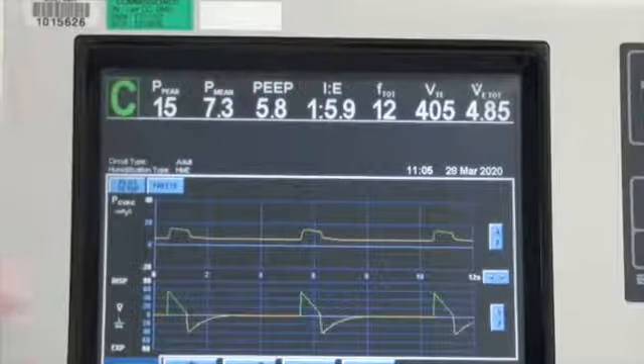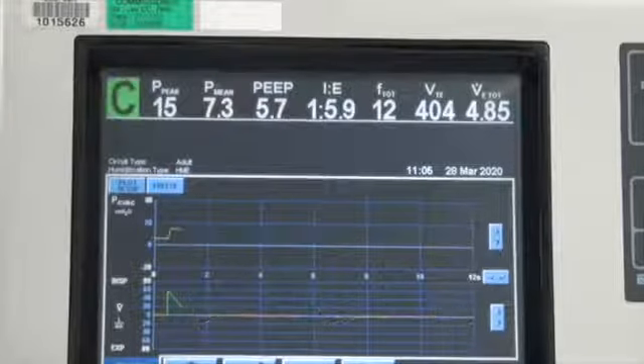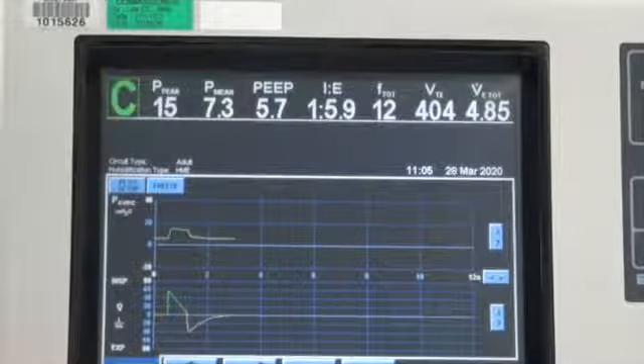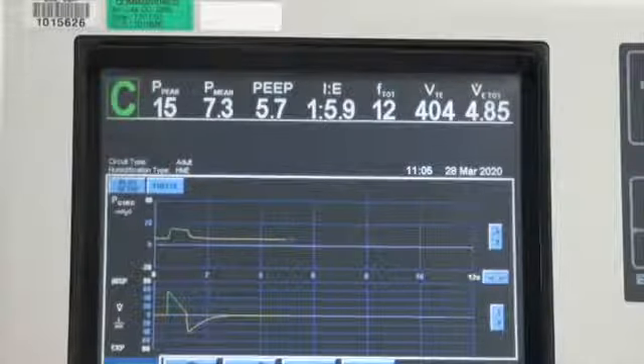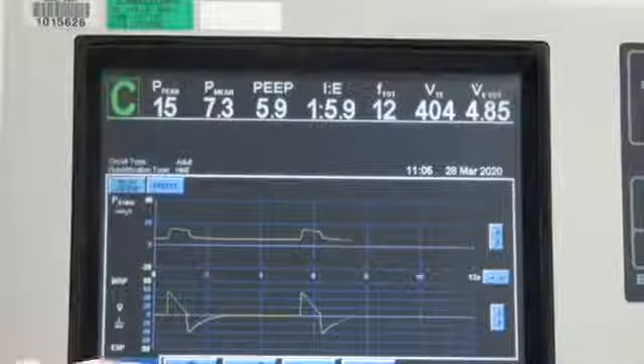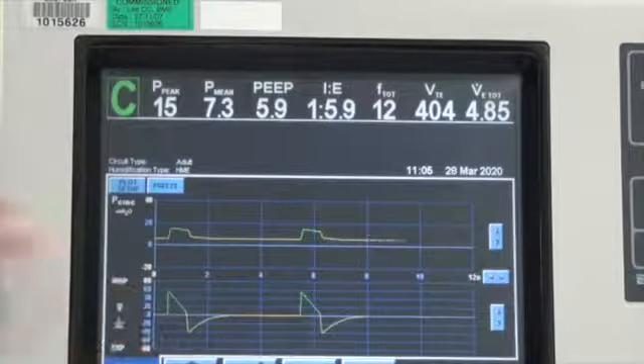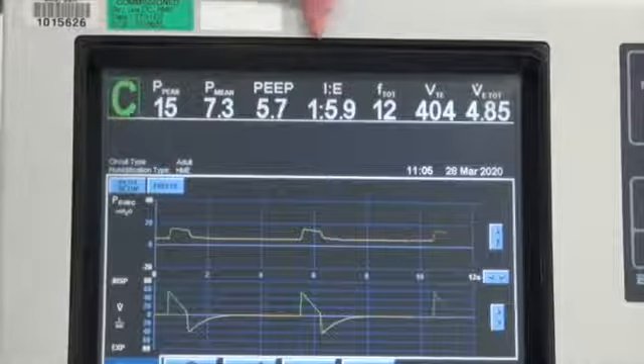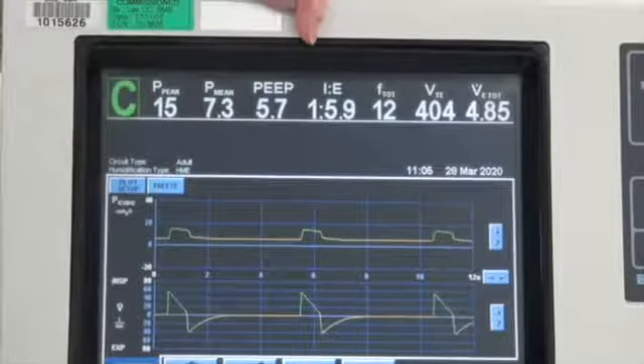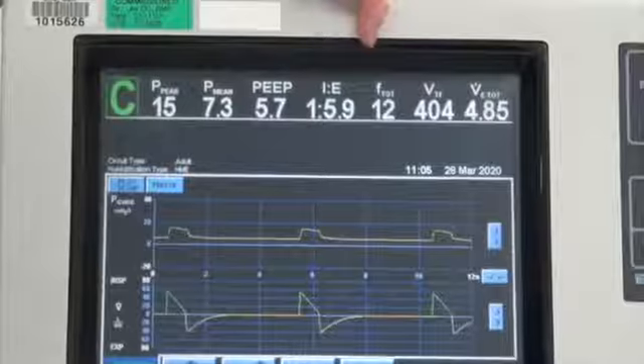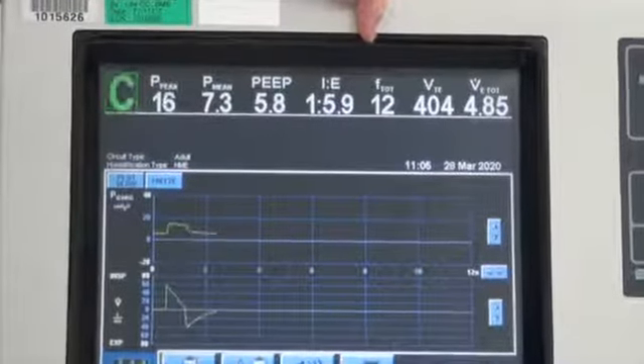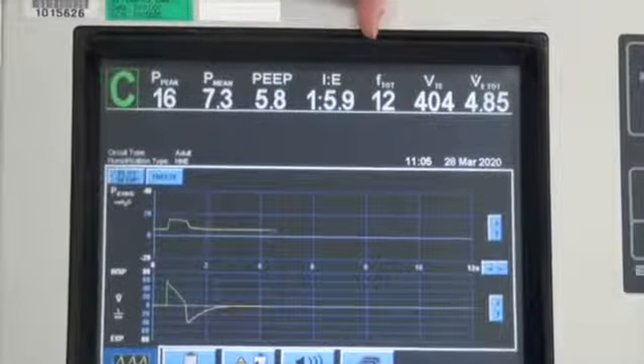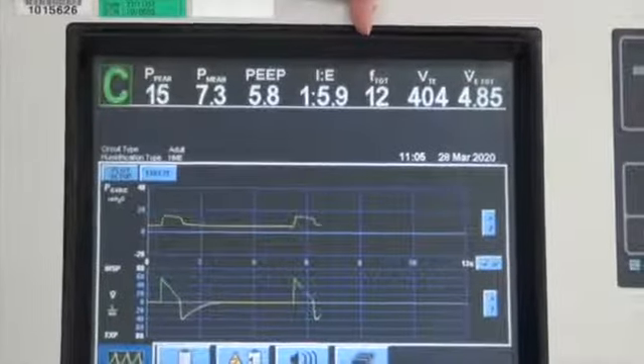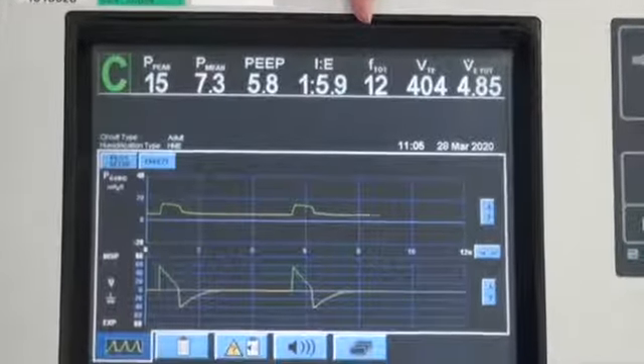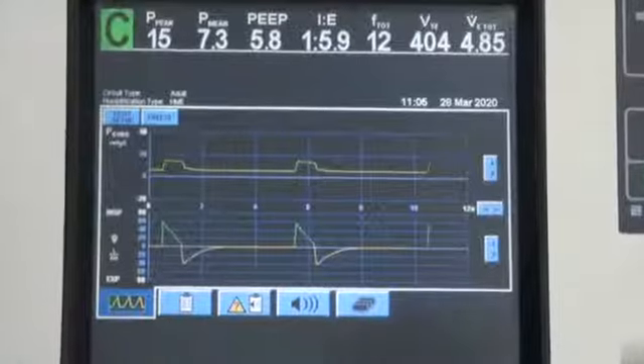Earlier on, I showed you how by manipulating the respiratory rate, volume, and the flow, it can actually change the ratio of the inspiration to expiration cycle. And this is continuously monitored and reflected in the reading above. The next button is the measured frequency. So in patients that are completely paralyzed, the patient trigger is entirely by the ventilator.